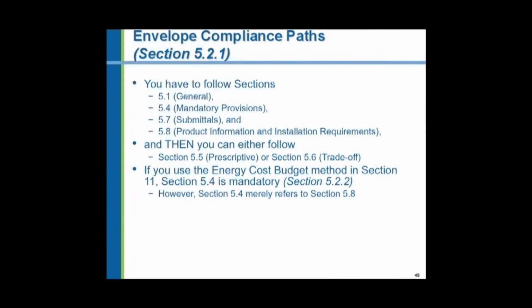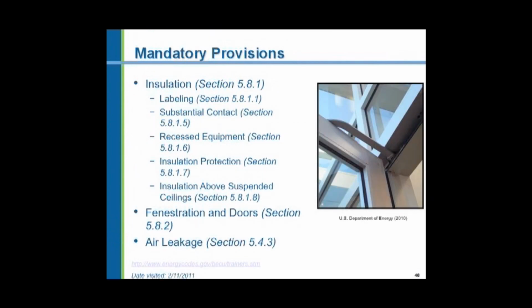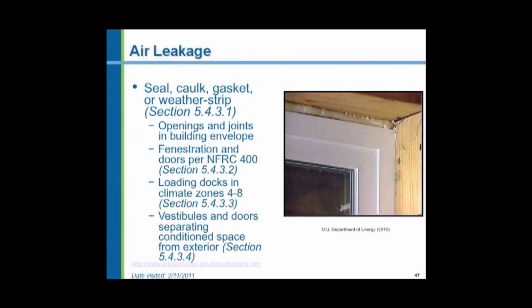Now, in complying with the envelope requirements, there are several paths to follow. You have to do certain things, mandatory provisions. Then you can do either the prescriptive or the trade-off. Or you can use a third one called the energy cost budget method. Those 3 methods. Some of the mandatory provisions are in insulation; all of these requirements, you have to label it. Substantial contact, recessed, we're going to cover all of those right there. And air leakage. Used to be that we would stuff scrap fiberglass insulation around the outside of a window during construction. Now we'll be looking at foaming that with an expanding foam, such as a polyurethane foam, to seal up the windows. We have to seal them in accordance with NFRC 400, National Fenestration Rating Council Standard number 400.